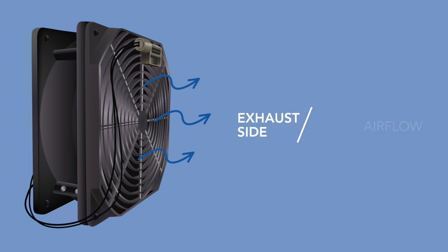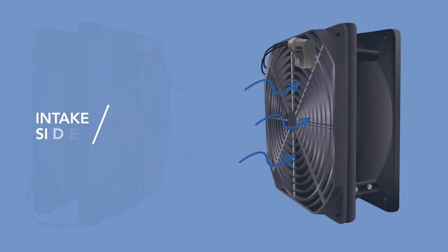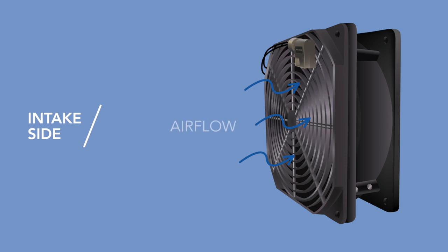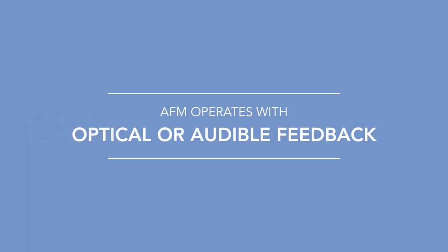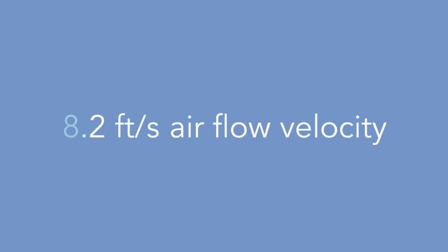positive airflow or to the intake side of the fan to measure negative airflow. The AFM operates with optical or audible feedback when airflow falls below 8.2 feet per second due to a fan failure or foreign objects coming into contact with the fan blades.